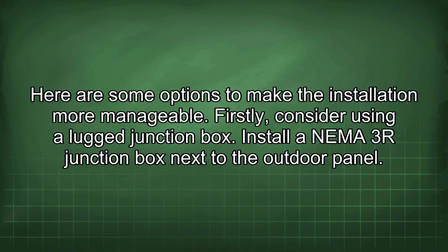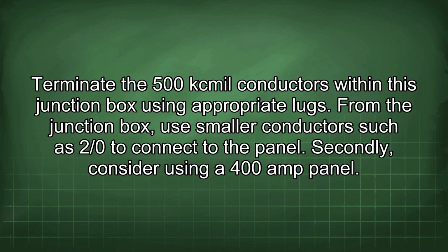Firstly, consider using a lugged junction box. Install a NEMA 3R junction box next to the outdoor panel. Terminate the 500 kcmil conductors within this junction box using appropriate lugs. From the junction box, use smaller conductors such as 2/0 to connect to the panel.